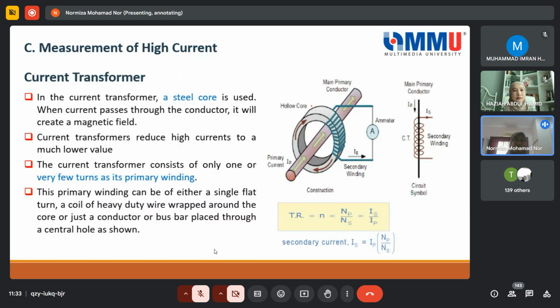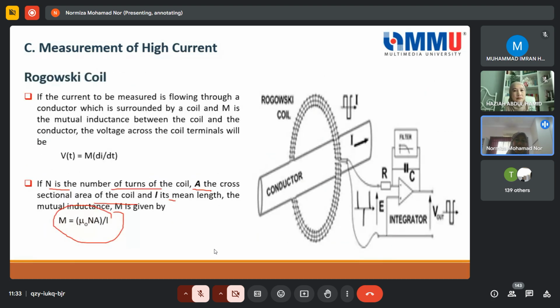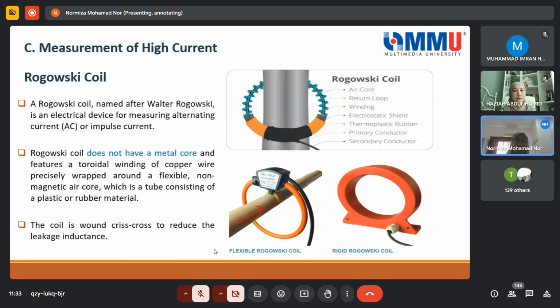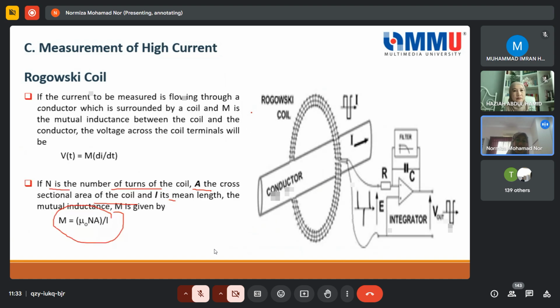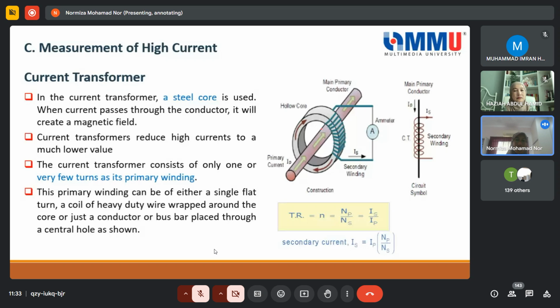Another type is the current transformer. It is slightly different from the Rogowski coil, because the Rogowski coil, as you can see here, doesn't use a metal core, but the current transformer uses a metal or magnetic core. In the current transformer, a steel core is used, which creates a magnetic field. Then the current transformer reduces high current to a much lower value.